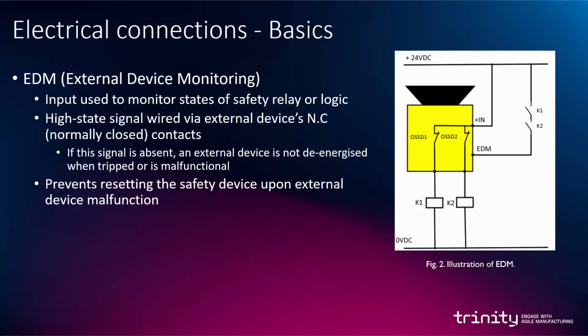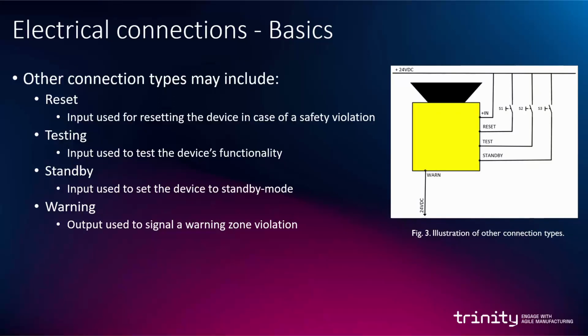malfunction. And other types of electrical connections that may be found on a laser scanner include reset input, testing input, a standby input, and a warning output. The reset input is used for resetting the device in case of a safety violation and is used to bring the device back to its normal operational state. The testing input is used to test the device's functionality, which may include switching the OSSD outputs on and off. The standby input is used to set the device to standby mode when needing to work with the monitored device, for example. The warning output is used to signal a warning zone violation, which can again be used to, for example, slow down the movement of a robot.